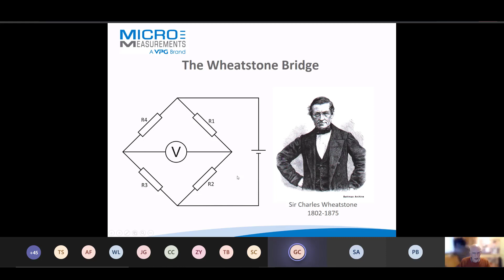If I move on a slide, I would liken it to your traditional kitchen balance, where if R1 and R2 are the same value - liken them to the same size of this weigh scale - if they have the same value, the pointer here will point to 0. Equally, if these two are the same, this point will be at 0, or halfway between the excitation voltage. Of course, if R3 and R4 are the same value, it will also be true this side as well, and therefore I'll have no output from the bridge. If I introduce an imbalance in one or more arms, then I will get a change of output.